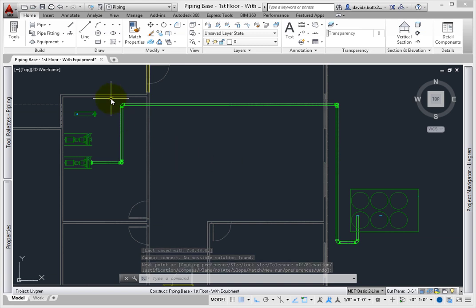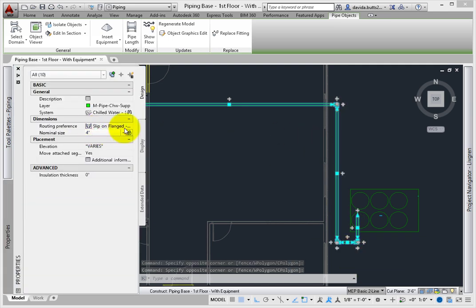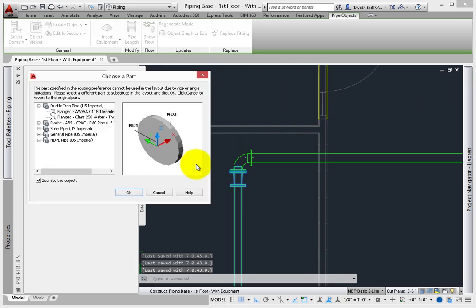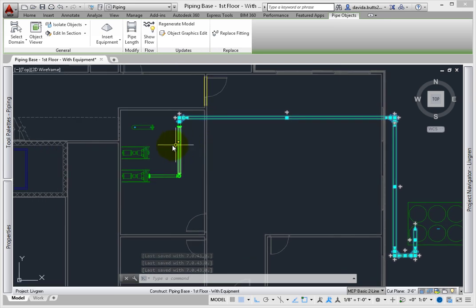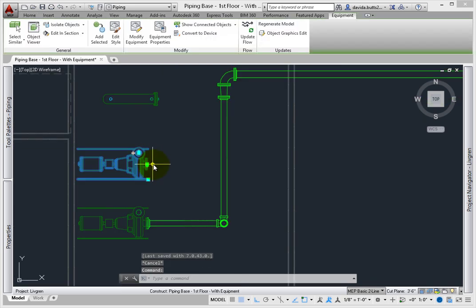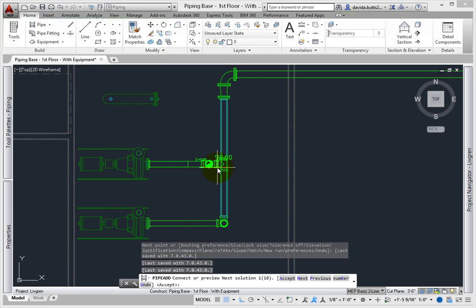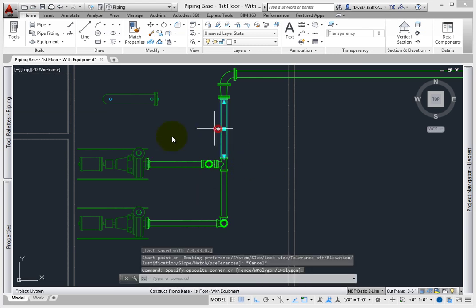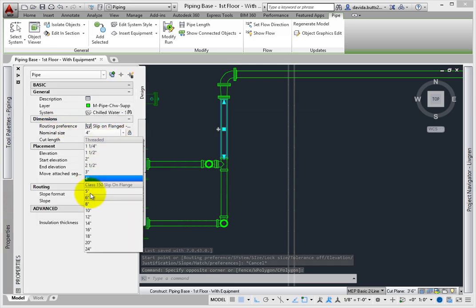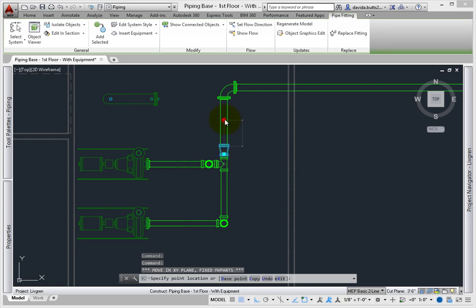If you don't like the sizes, pick a few pipe segments and change the size to 5 inches to match the connection. Accept the default reducer, and then go look at the pipe — the corrected fittings were changed to flanged based on the routing preference. To create a branch, pick the other pump and then pick the plus sign grip on the suction face. Add a short leg for the branch, and then pick the main pipe. You may get a large number of routing solutions, so pick the one that shows 90-degree fittings. Type A to accept, and then press Enter. Resize the pipe to the T at the pump connection and add the reducer when prompted. Pick the reducer and drag it up near the elbow — notice how easy it is to relocate fittings. These techniques work well as long as you have enough room to create the fittings.